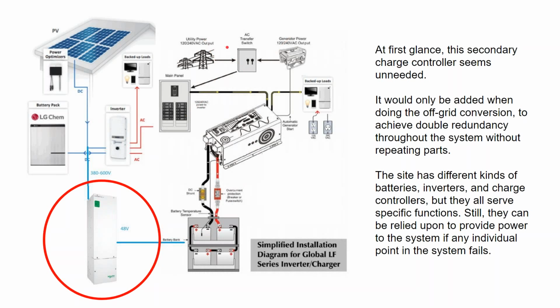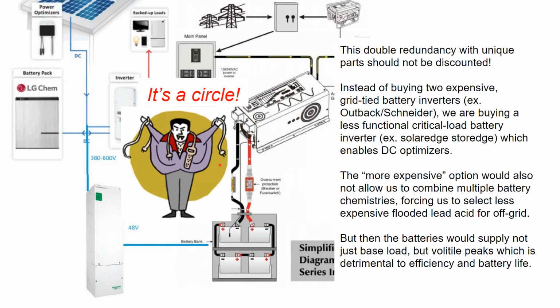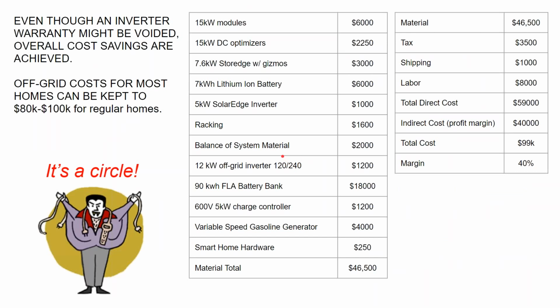Then you could cut the grid out and switch your battery inverter into a demand management profile, having your lead acid provide your base load and your lithium ion provide your peak or dynamic loads. So all of that stuff works, it's just not supported by the manufacturers, who are really only focused on one particular application, whether off-grid or grid-tied products. There's not really a comprehensive system.